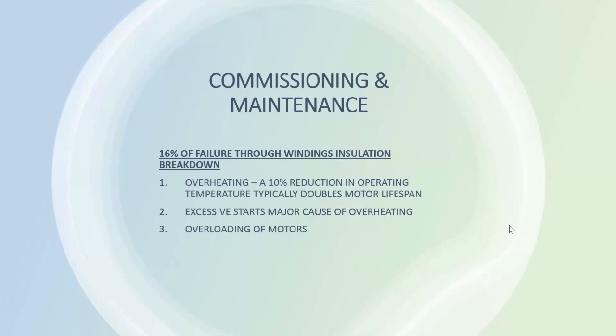And excessive starts cause major overheating. So you select your correct motor. If you need a design type C, you select it so that you avoid frequent trips. When frequent trips are avoided, you avoid frequent startups, and your motor will not be overheated, and you have your motor running for a longer time. Overloading of motors: we must ensure we put in the right overload setting so that motors can operate, and it has a breathing space of about 20%, so that when there is even an overload, the motor will be able to accommodate it.